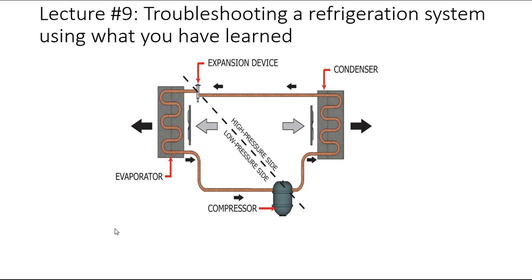One of the biggest time savers you can ask a customer, especially if you're dealing with an air-cooled system, is when was the last time you did maintenance. We have air flow going across the evaporator and across the condenser. Before you ever get your gauges out, you want to make sure your air flow is clear, because more often than not, you may think you have a refrigeration problem, but it's really a maintenance problem. Make sure there's no restrictions, because it will cause your readings to be really messed up.